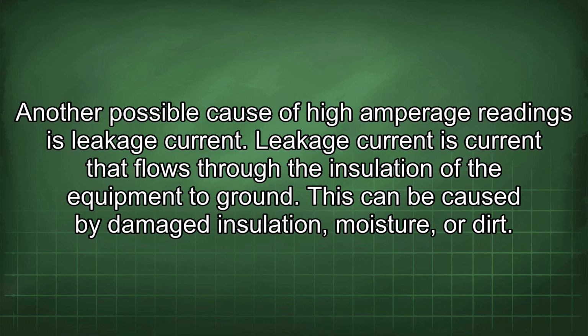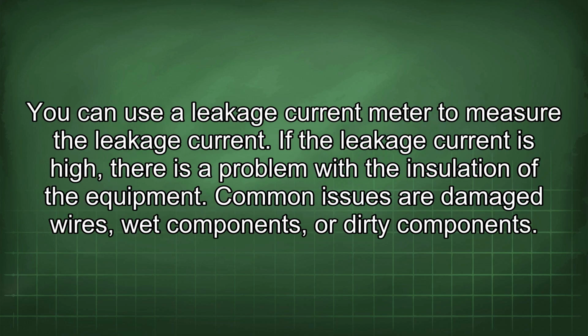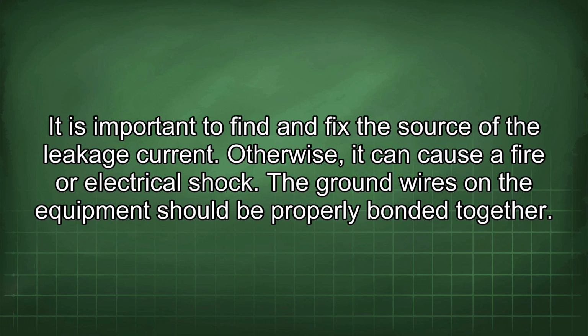Another possible cause of high amperage readings is leakage current. Leakage current is current that flows through the insulation of the equipment to ground. This can be caused by damaged insulation, moisture, or dirt. You can use a leakage current meter to measure the leakage current. If the leakage current is high, there is a problem with the insulation of the equipment. Common issues are damaged wires, wet components, or dirty components. It is important to find and fix the source of the leakage current. Otherwise, it can cause a fire or electrical shock.